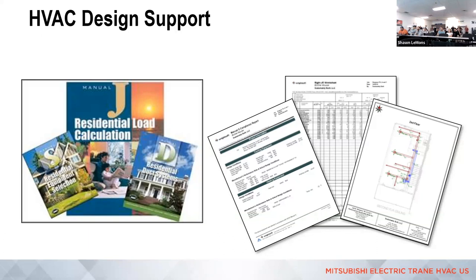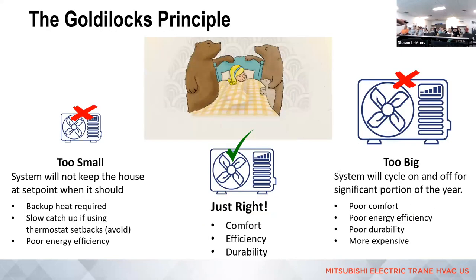All this is doing is looking at the insulation level of the ceiling, the walls, the windows, the floors, your air leakage rate, and what's inside the house producing heat or taking heat away, like ventilation, things you plug into the wall, people, appliances, et cetera. All that gets worked into the Manual J and comes up with a load. The goal is to not oversize it and not undersize it.